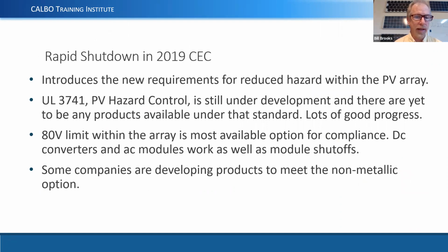And so UL 3741 is a new standard, PV hazard control. This is actually an old slide, so it's not still under development. It has been voted on and is available. There are a few products out there that have passed PV hazard control stipulations. That standard will be under some revision over the next several years just because it's very new and very complex. There's probably half a dozen products currently on the market that have this PV hazard control listing, and it would include some Tesla products, some SolarEdge products, some Enphase products. So there's been some really good progress there.